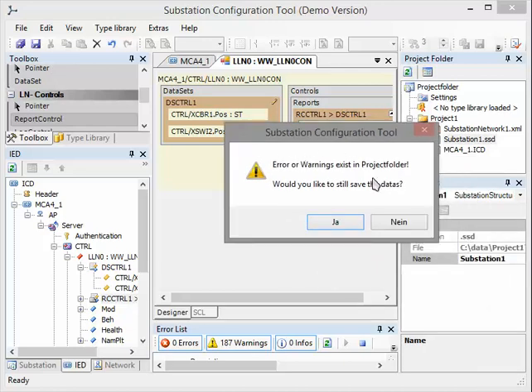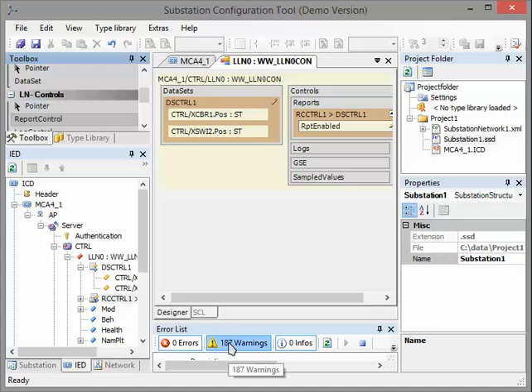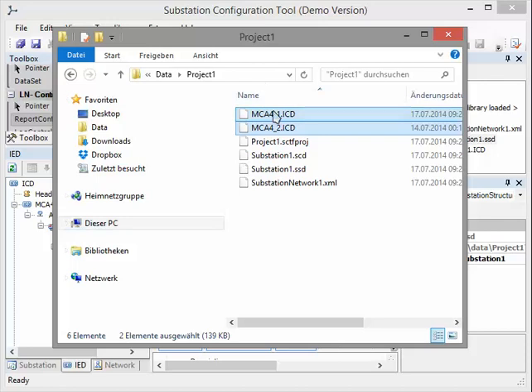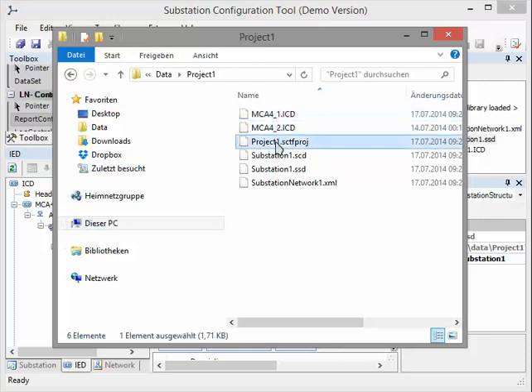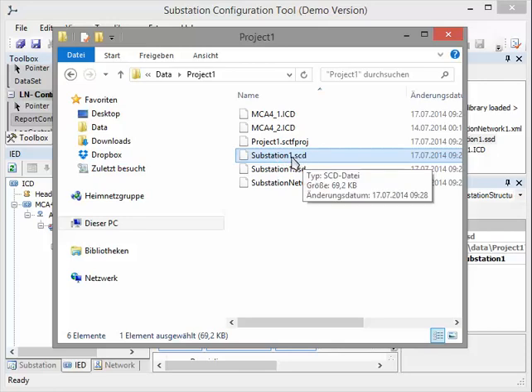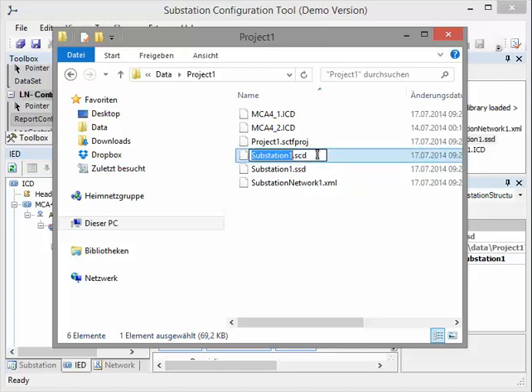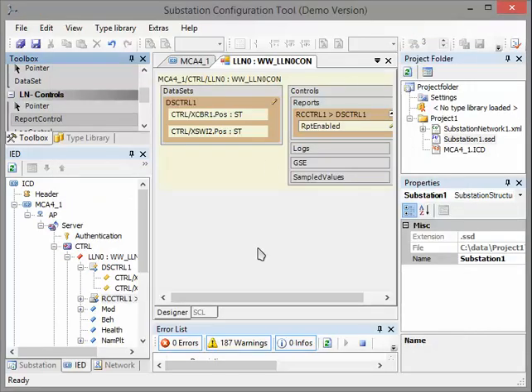It will tell us there will be some warnings — you will see them here. There are warnings but no errors. We say yes, save. Warnings are not a problem — they only indicate that something is not ideal, not a real fault. If you have errors, you must check your configuration because something is wrong and the file will not be created. Inside of our project folder you can now see our ICD file, the project file, the network file, the substation file, and most importantly our SCD file. SCD means Substation Configuration Description, and this file you will transmit to your protection relays to give them the information for the substation configuration. I hope you find this video entertaining and educational. I wish you a nice configuration in your future. Thank you.